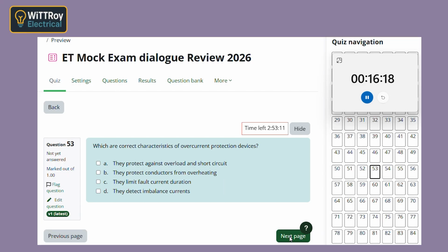Question 53. Characteristics of overcurrent protection devices. They protect against overload and short circuit? Yes, that is the core idea. Let's connect the logic. If too much current flows for too long, conductors heat up. Overcurrent devices interrupt that current before damage becomes severe. So they protect the cable and the equipment from overheating.